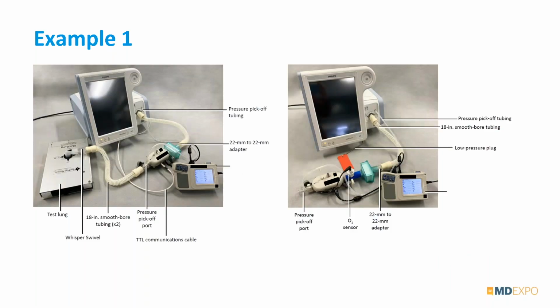This is an actual couple of photographs from a ventilator manufacturer's service manual. And they've done a fairly good job of showing you how to set up your test equipment with their ventilator. But of course, they've chosen one piece of test equipment. You may have others. You may have to adapt this photo to your equipment. They've done a pretty good job with showing all the components. You've got the analyzer there, and you've got all the connections to the ventilator, including the pressure connections.